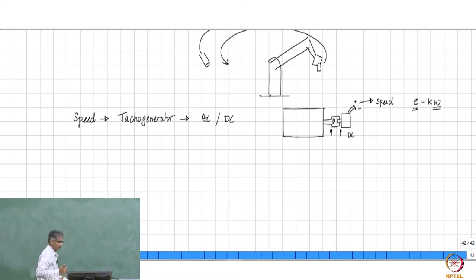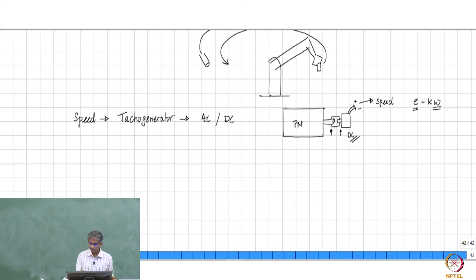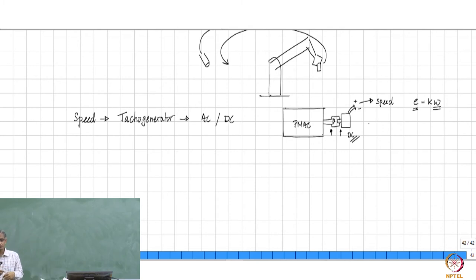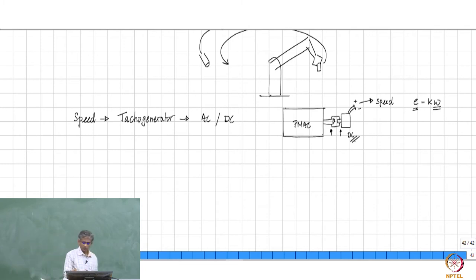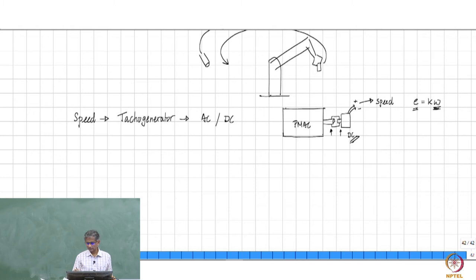The difficulty with a DC tachogenerator is that it is still a DC machine, so you have to replace the brushes and service it even if the main motor is an AC machine. Though this is a very good mechanism to sense speed because you get instantaneous velocity in either direction, there is sometimes a hesitation to use it for speed sensing.